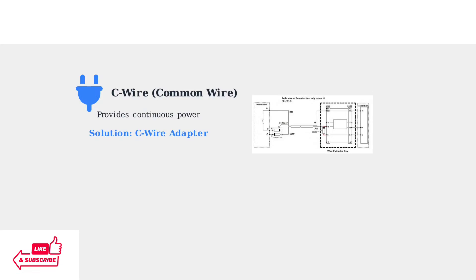The most common cause of a blank display is a missing or improperly connected C wire. The C wire provides continuous power to your smart thermostat. If your home lacks a C wire, you'll need to install a C wire adapter. This diagram shows how to add the necessary wiring for proper power supply.